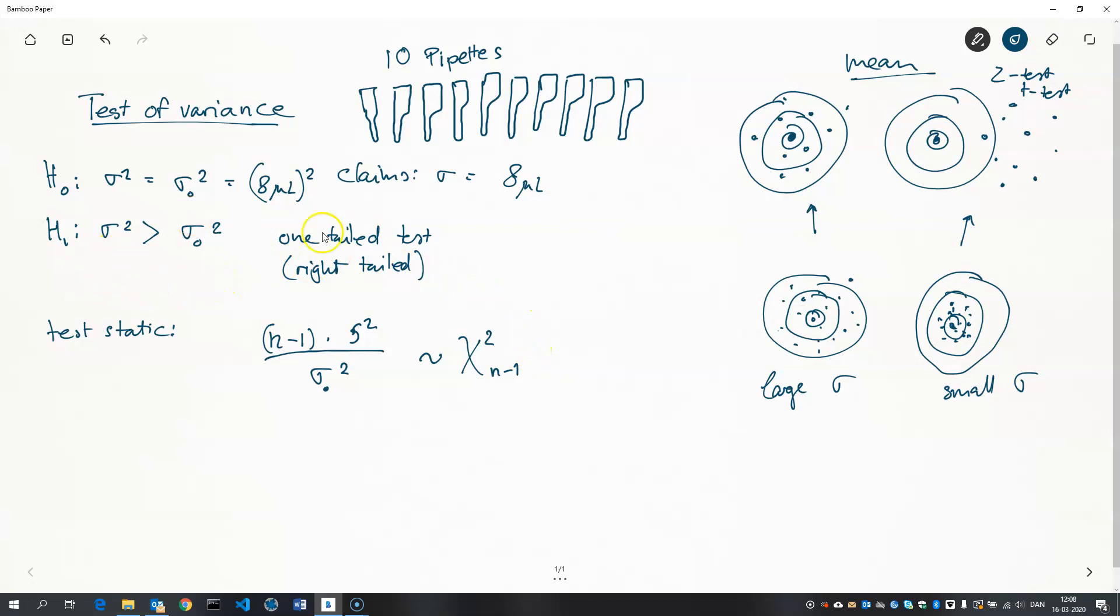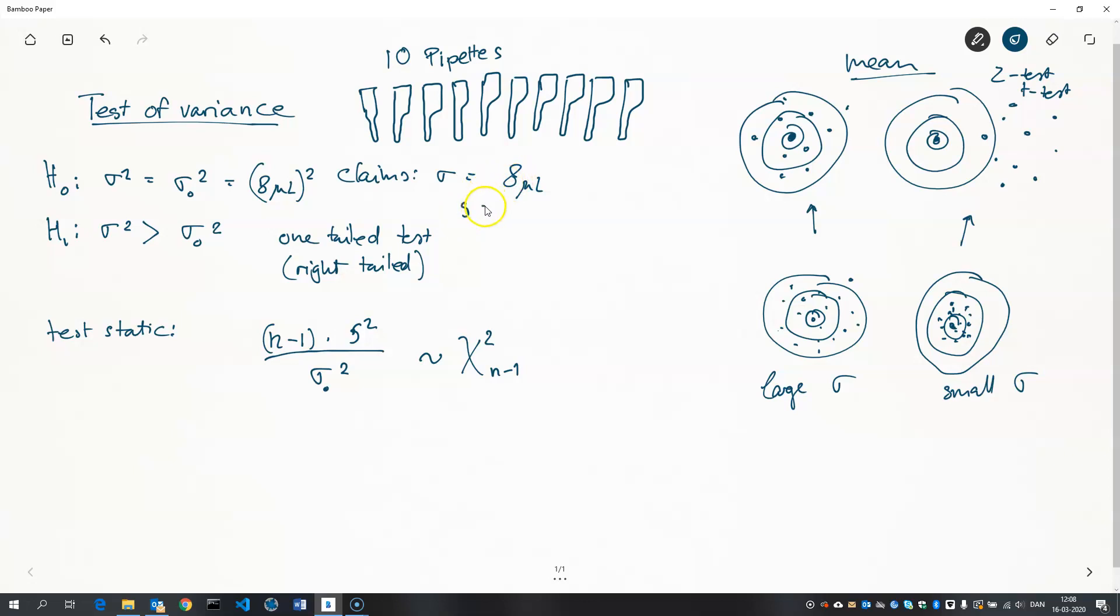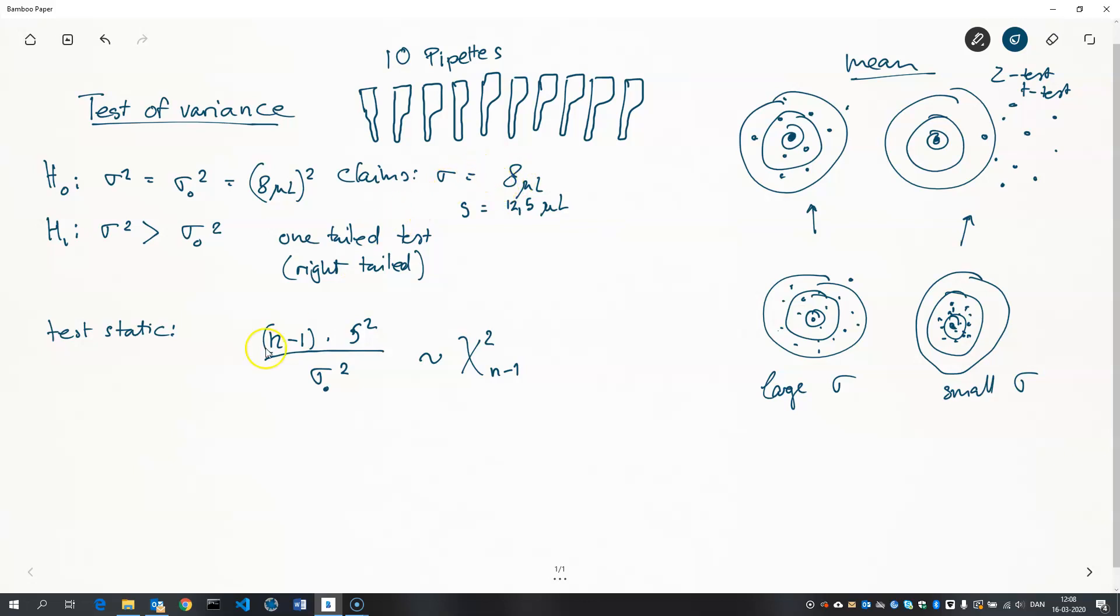So we need to take our sample here and compute the sample standard deviation from this, or the variance, if you like. And let's just assume we did that. So, it turned out that the sample standard deviation was 12.5 microliters. So that's quite a bit above what the manufacturer claims, but that could be a matter of chance. Bad luck, if you like, but we'll have to do the test to see if that's true.